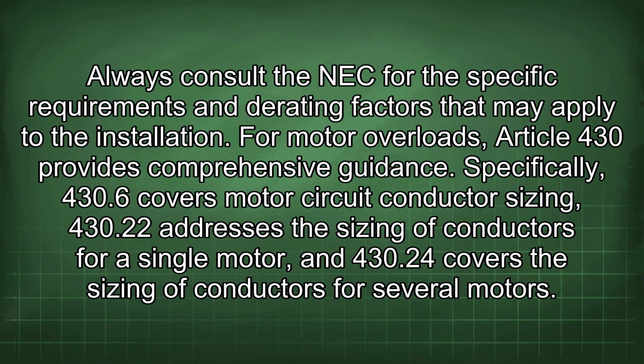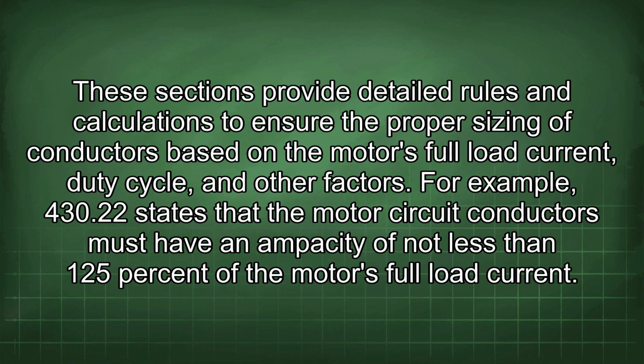For motor overloads, Article 430 provides comprehensive guidance. Specifically, 430.6 covers motor circuit conductor sizing, 430.22 addresses the sizing of conductors for a single motor, and 430.24 covers the sizing of conductors for several motors. These sections provide detailed rules and calculations to ensure the proper sizing of conductors based on the motor's full load current, duty cycle, and other factors.